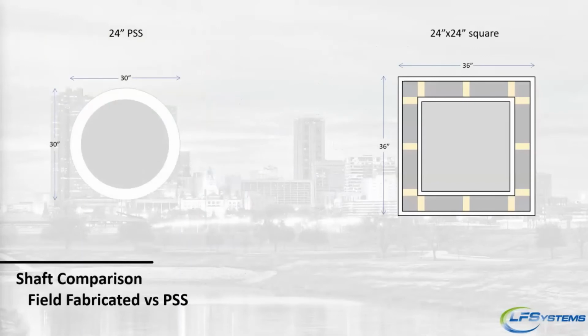So a standard 24-inch square shaft is going to actually require 36 by 36 inches of available space, because you basically have 1 inch worth of sheetrock, a 4-inch gap for the studs, and another 1 inch of sheetrock on both sides. So now you're gaining 6 inches on both sides. With us, because we're only 3 inches, that 24 by 24-inch round pipe, with 3 inches, is only 30 by 30.